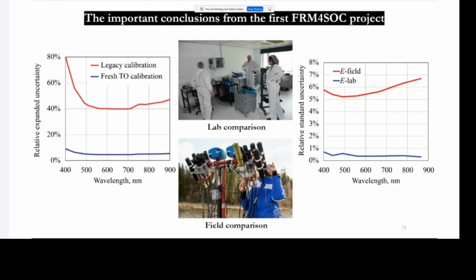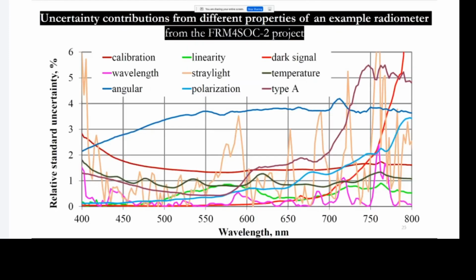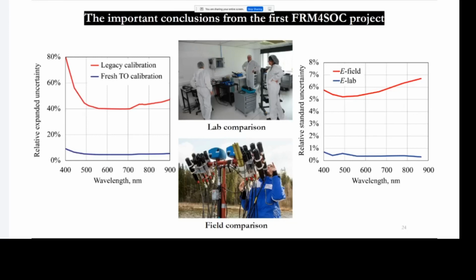This happens because each radiometer has its individual characteristics, and those characteristics react differently to the conditions in the field. Those conditions, the spatial distribution, spectral distribution, and the ambient temperature, are different from the lab setup. So with this second graph, the conclusion is that calibration is very good, but calibration alone is not enough to ensure the quality of the measurement. The instrument has to be individually characterized as well to achieve low uncertainty. These are some important findings of the first FRM for SOC project.